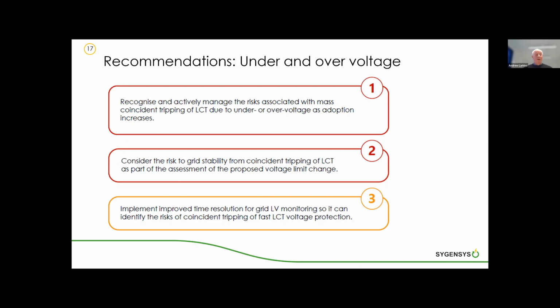And finally, what we would highlight is that improving time resolution of low voltage grid monitoring is an important aspect. We have struggled to find any substantial data source which provides good voltage and time resolution of voltages on the LV grid, looking at the response time for EV chargers. So being able to detect under and over voltages on the timescale of a second to a few seconds. And increasingly, as we end up with more devices connected to the LV network with under and over voltage protection operating within a matter of seconds, it's important that we recognize that there is a need for data gathering right the way from transmission level down to distribution and LV network.